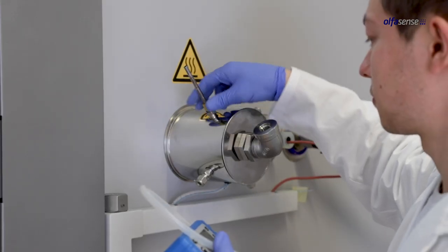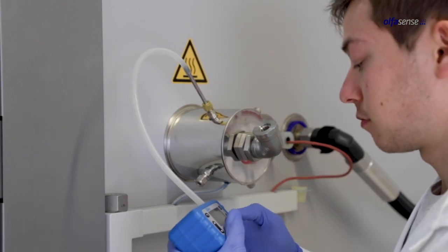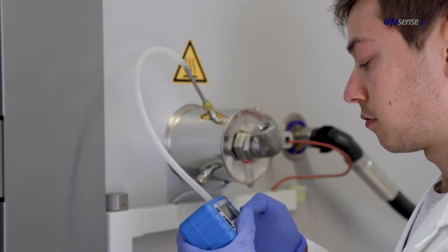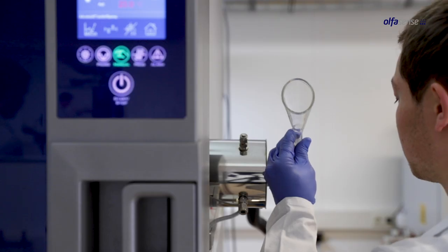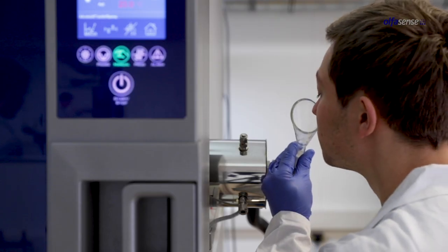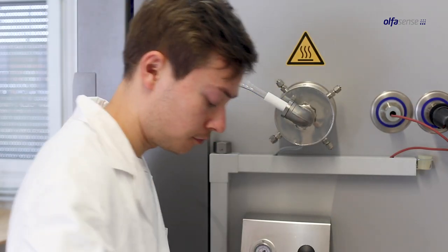The EK1000VOC emission test chamber allows for a broad analytical performance spectrum via four heated sampling port connections. In addition, a nose mask can be mounted directly on the test chamber sampling port, which is required for some measurement standards.